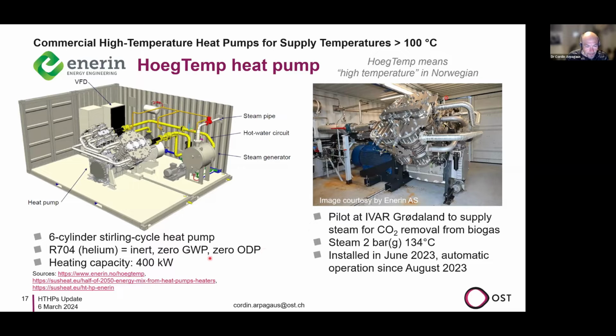This system has a 400 kilowatt capacity and also produces steam. Here we see a steam generator from the company Vahterus from Finland, connected to the heat pump. This is an example of a pilot running at a company called IVAR, which works with biogas and needs steam for CO2 removal from biogas. This heat pump produces 2-bar gauge steam at 134 degrees. It was installed in June 2023 and is now operating.